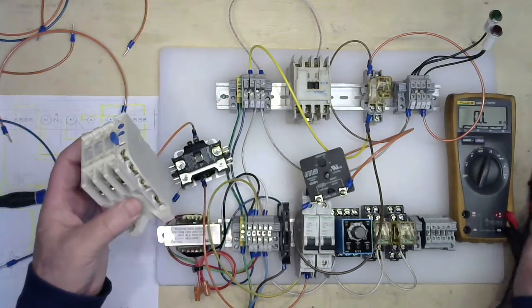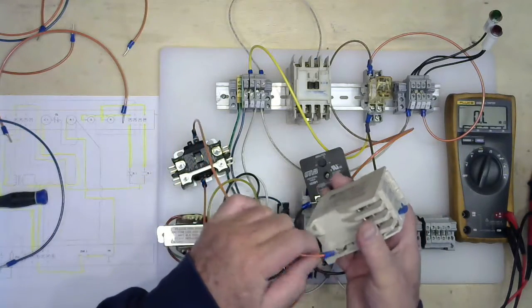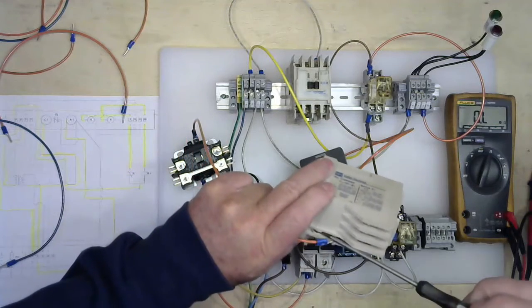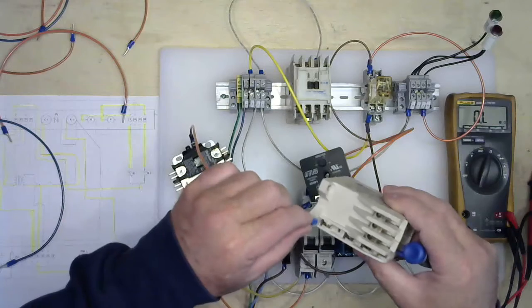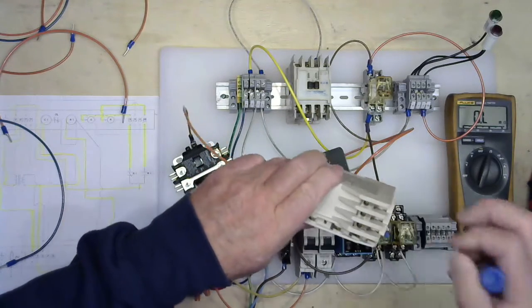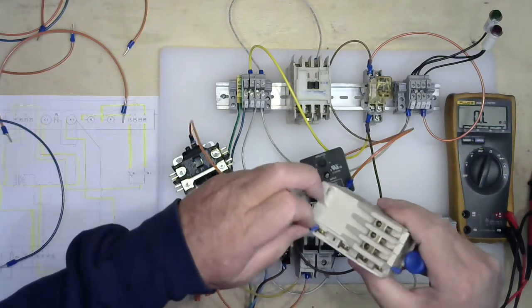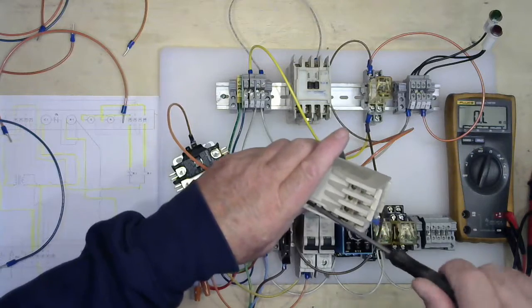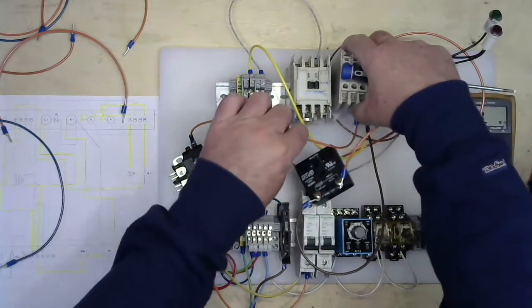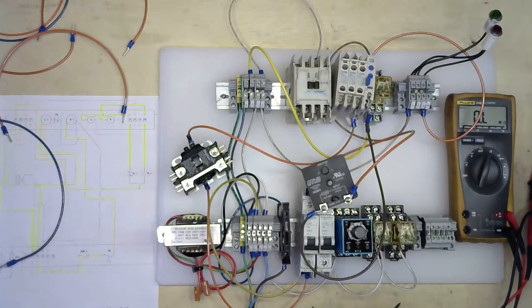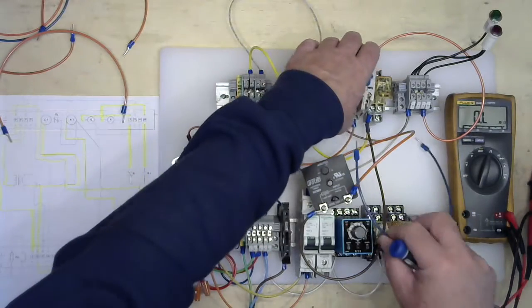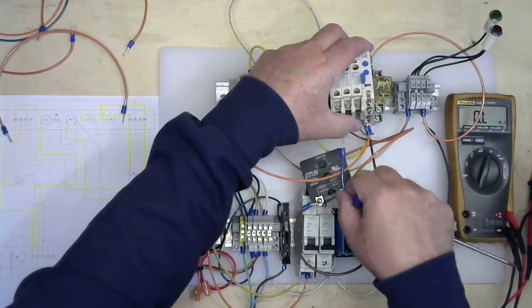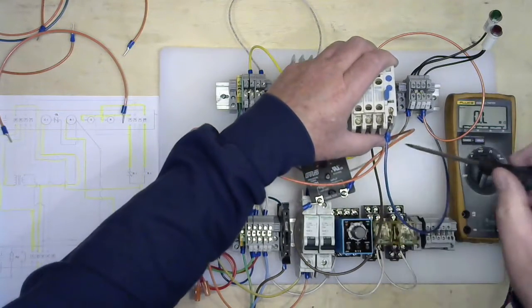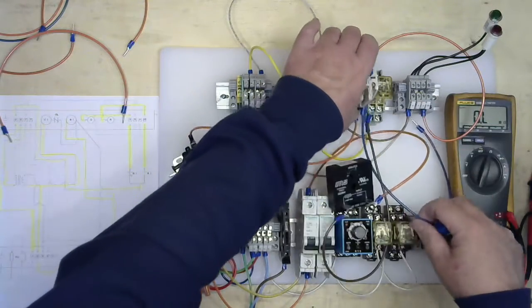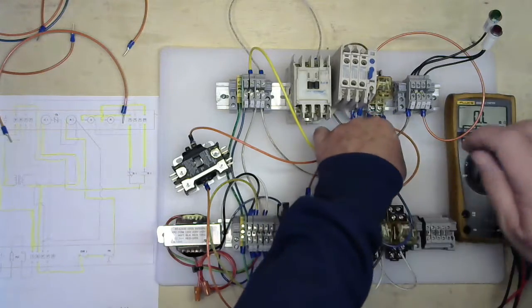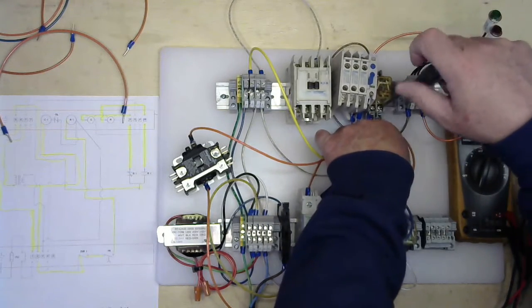So I've got to make sure that as I leave my coil here, I'm going to go into, I'm going to use this bottom one. And again, doesn't matter which one, doesn't matter if it's 95 or 96 first. I'm going to go into the bottom one and connect my neutral wire into my bottom contact. And your particular ones, this will be fastened to the board. Again, this is the only one I have that doesn't have the connection point on it, so I'm just holding it for reference for you. I'm going to take another wire out of there, and I'm going to leave 96. I originally connected 95. You can look on your own block. Connect that here. It's going to go to my relay coil.